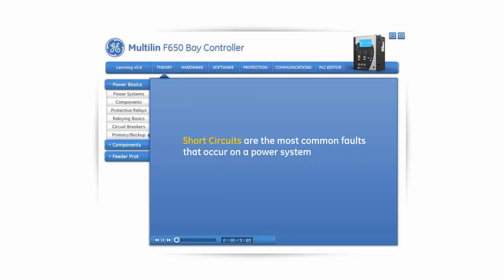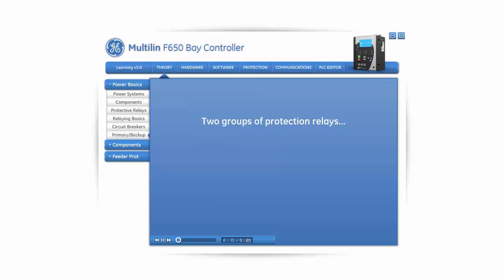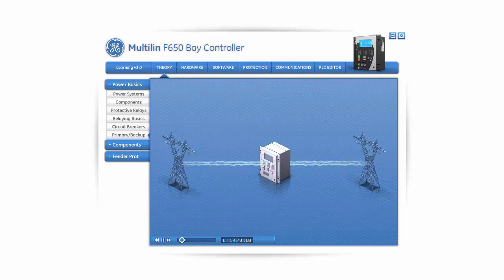We will now consider relays that are dedicated to protection against short circuits. There are two groups. The first group is called primary relays and is the first line of defense, while the second is called backup relays and functions only when the primary relaying fails. Backup relaying can be classified as either local or remote. Faster reacting backup relaying can be achieved by using local backup relaying systems.